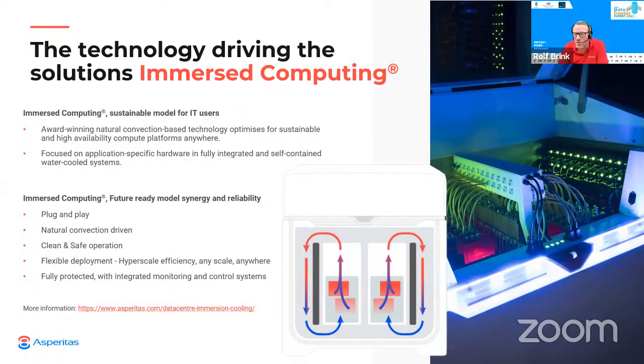IT equipment is immersed into the fluid, with the hottest components like CPUs and GPUs as deep in the fluid as possible. The heat provided by these chips warms up the fluid, making it expand and rise to the surface. Within the same dielectric bath, there are water-cooled heat exchangers connected to the facility water circuit, enabling cooling of the dielectric fluid. This generates higher density fluid, which makes it sink again. This allows a natural convection circulation that is pumpless, driven by gravity, and allows high efficiency operation without any moving parts.